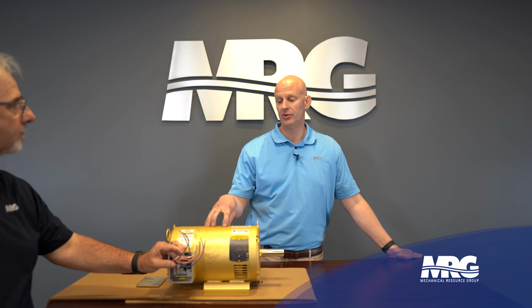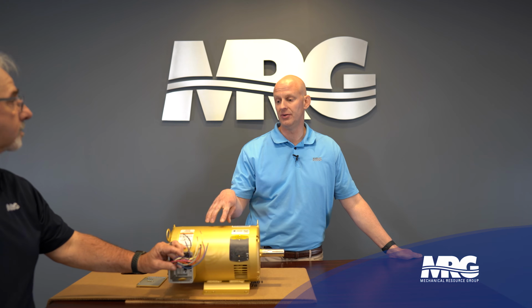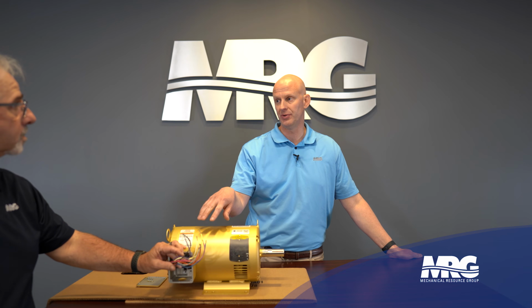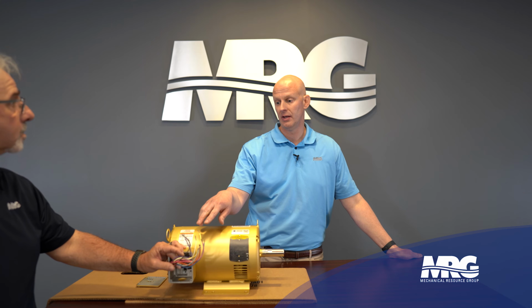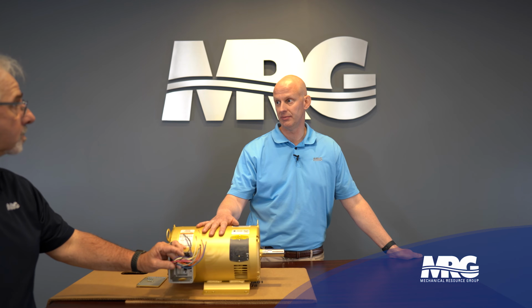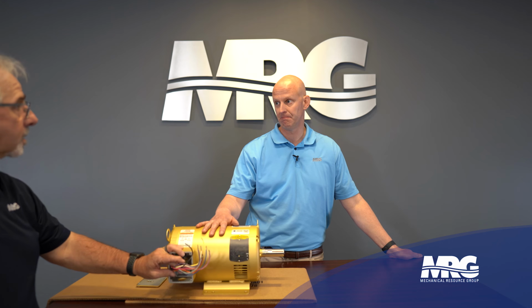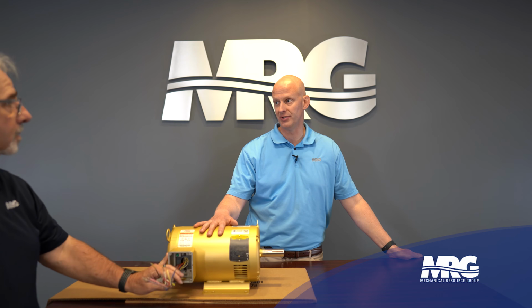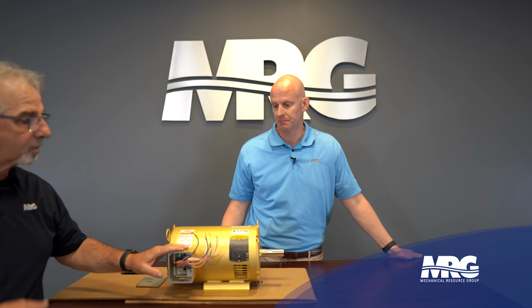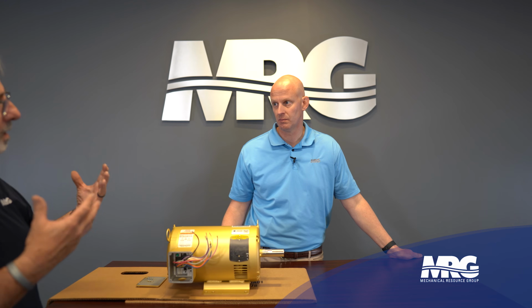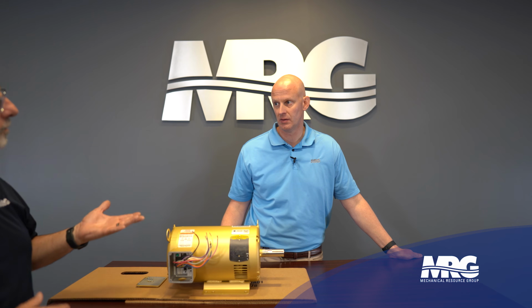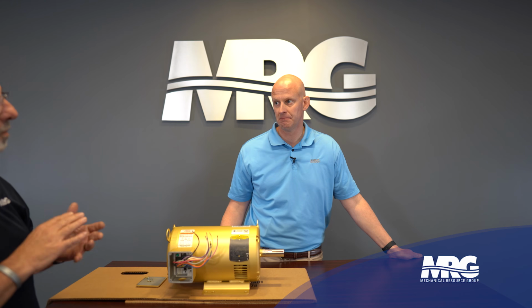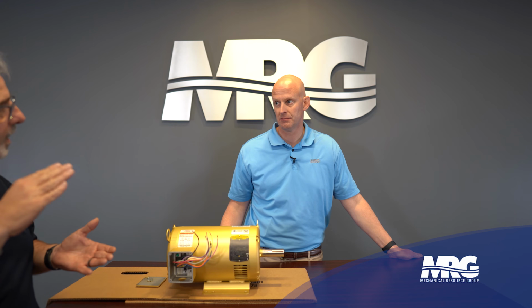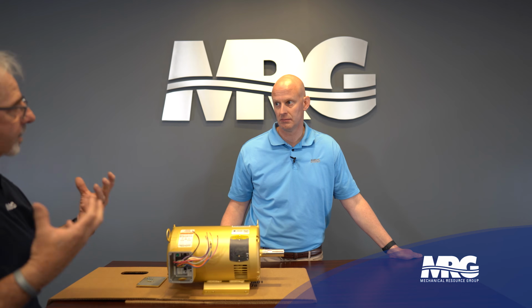And if you do have a soft start or a VFD, and you do a reduced voltage wire at the motor, you're jeopardizing your motor long term. Oh yeah, definitely, because you're not getting the full juice out of it. Remember, reduced voltage is the same physics law: lower the voltage, the higher the current. So we want to move that voltage up to the highest point that the motor is rated for as quickly as possible, but still get that soft start.